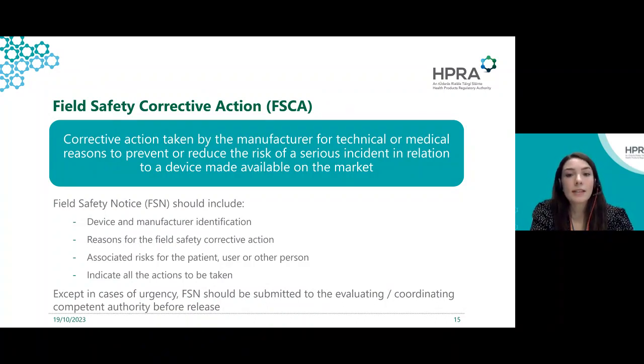A field safety notice, then, is a communication that informs customers or users of an FSCA, and this must follow a template as well and must include information relating to the device and manufacturer identification, reasons for the field safety corrective action, associated risks for the patient, user, or other person, and indicate all the actions to be taken. The draft FSN, where possible, should be submitted in advance to the coordinating authority. The coordinating authority for a field safety corrective action is usually the competent authority of the country where the manufacturer or the authorized representative is based. That's linked to where the manufacturer has their location, and they would be coordinating for the rest of Europe.